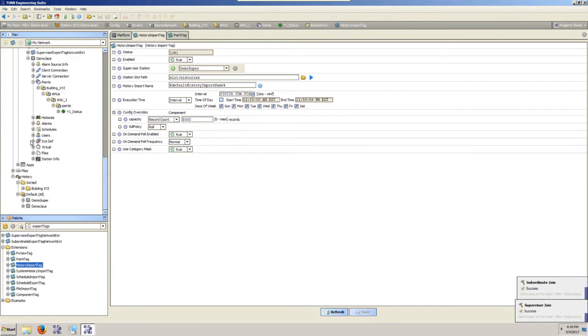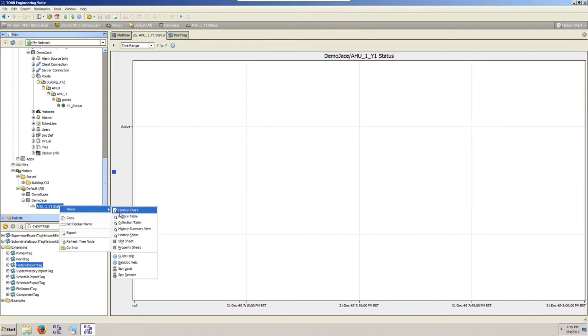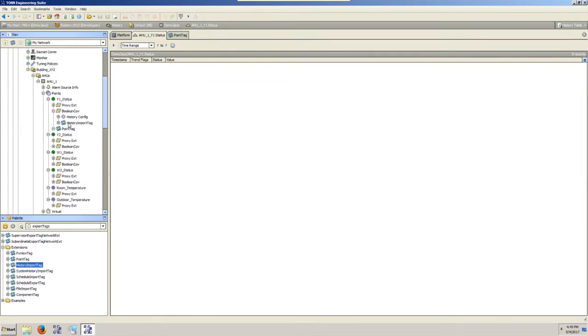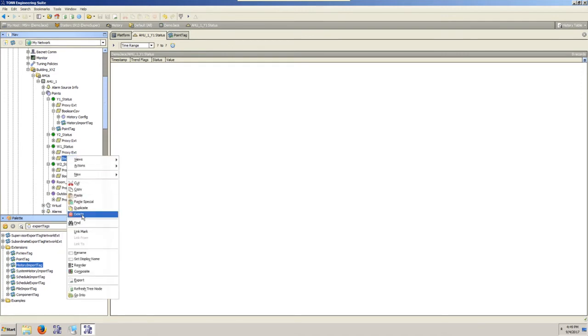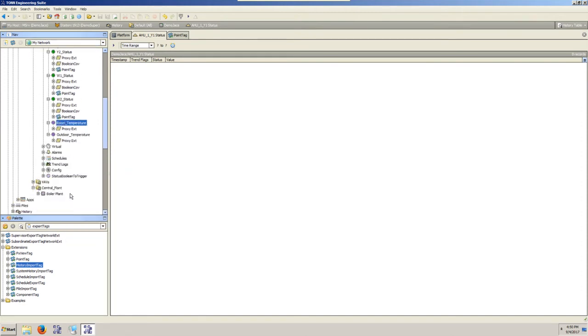So we had the success. We know that worked. You'll see that we do have the jace here now. There's our data log. Probably not much in there, as I just set everything up. Not anything. Good enough. So normally if I was starting a jace and these are points I just pulled in fresh from a discovery, I would normally grab the history, grab the point tag, and basically just copy and just plop these things on here. Everything's using B format to set the actual names. So there's no reason that you can't just plop them in.